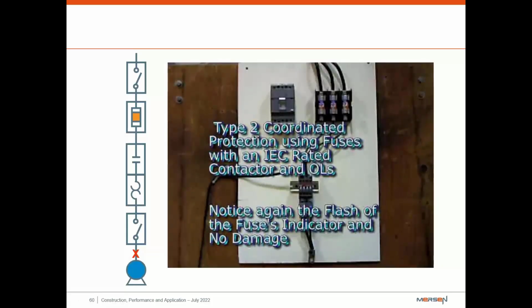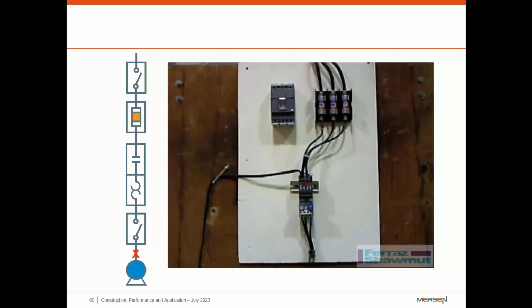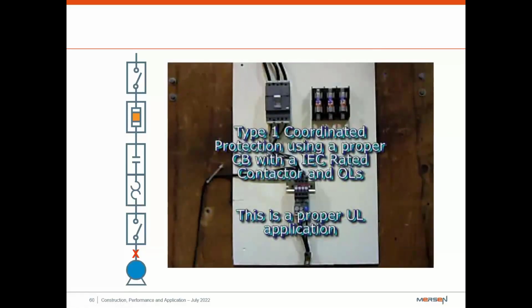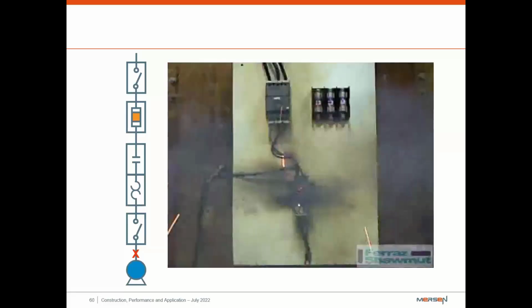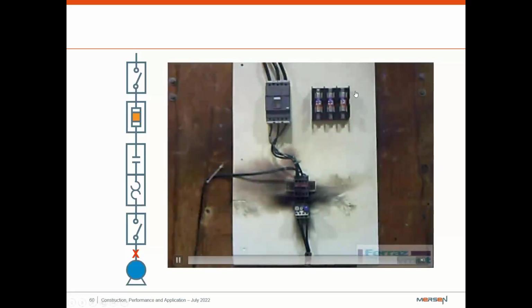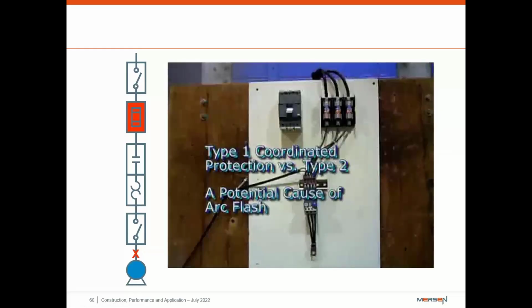Now, type 2 coordination protection with fuses and an IEC contactor with an overload relay. Notice again that there's going to be a flash on the indicators for the fusing in this application. See, now that it's safely open, no damage to the overload relay, the system worked just fine. Now, type 1 coordination protection with a proper circuit breaker and an IEC rated contactor for an overload. This again is also a proper UL application. So you can see the difference. The fuse actually opened to protect the overload relay, where the breaker did not. Now, I believe some of the newer, smarter breakers out there might be able to handle this, but fuses are going to be the route. They're going to be the way to help you so you're not damaging any equipment that is actually involved in the system. Now, the difference between type 1 coordination protection and type 2.